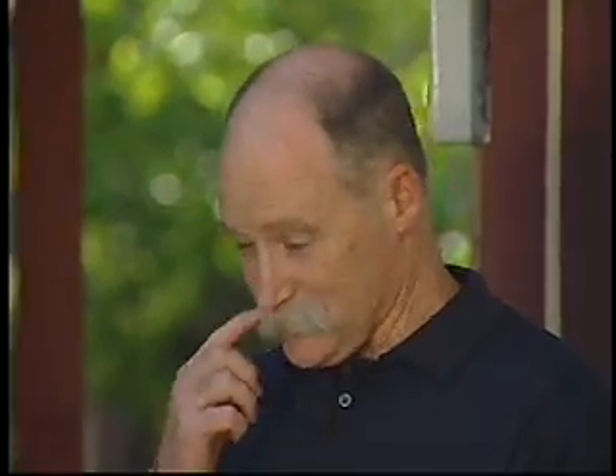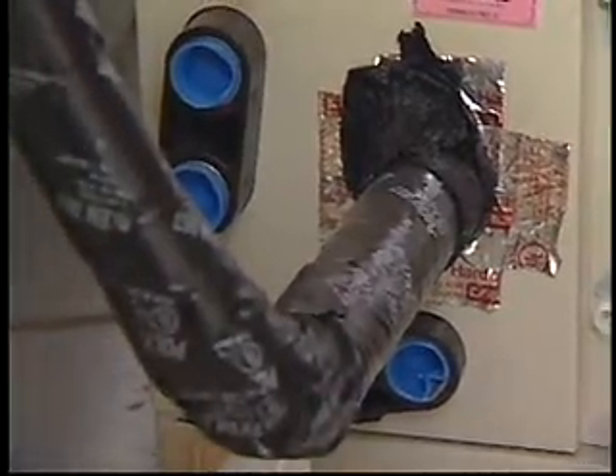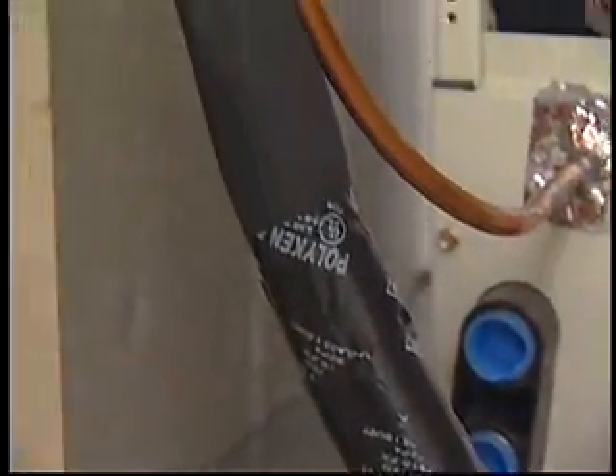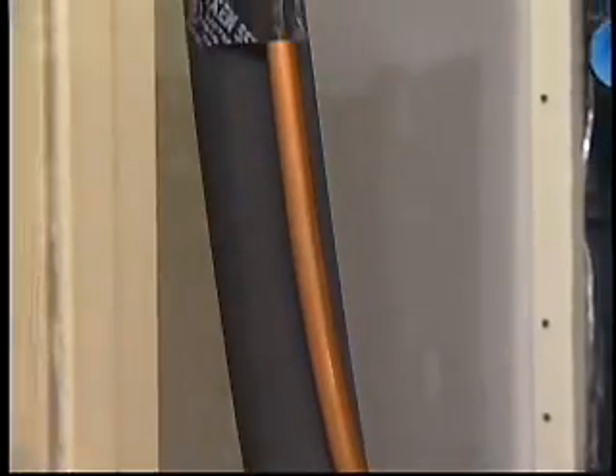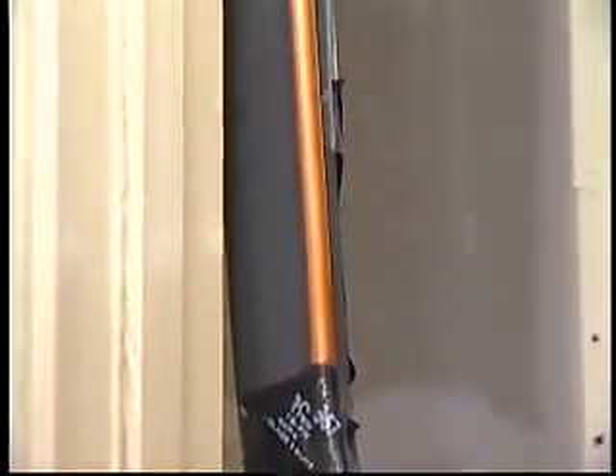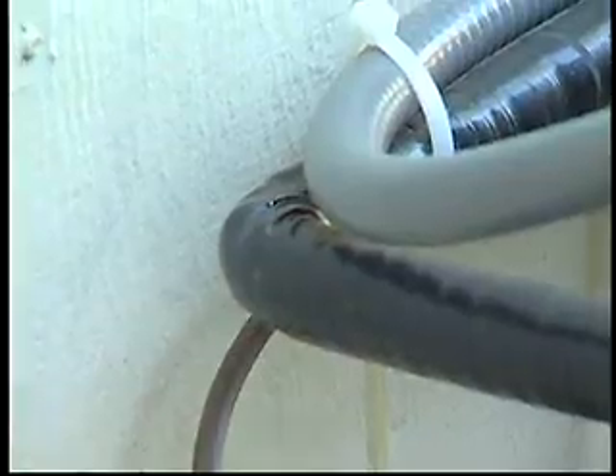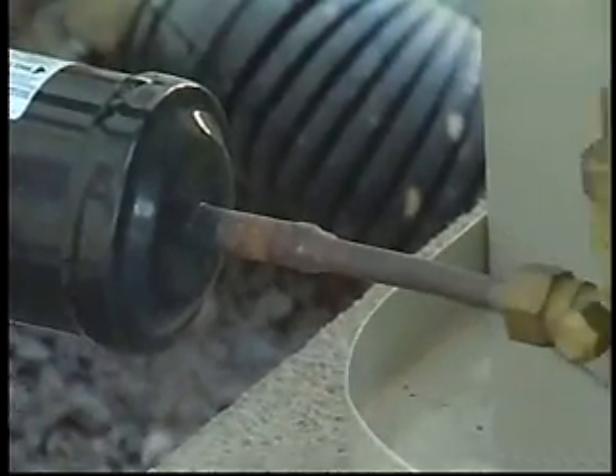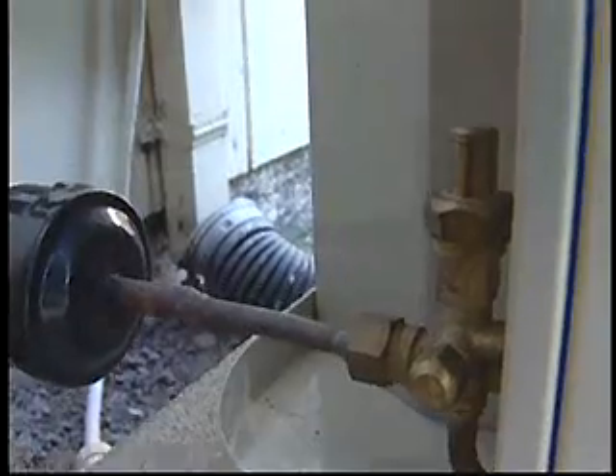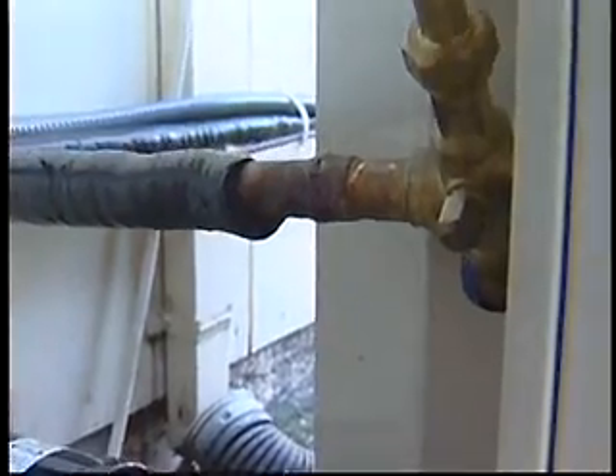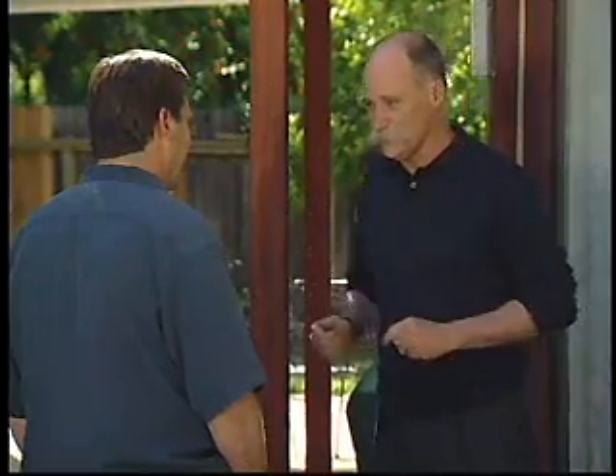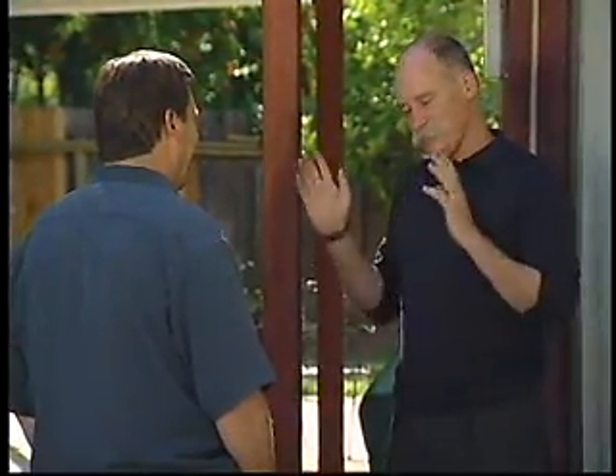What about the size of the line set itself? Sometimes it seems like they run some awful long line sets. Yes, as the line set gets longer, you have to change the diameter of the line set. And again, that's something that all the manufacturers specify, but is most often ignored. In fact, one of the things that you often find is that coming out of the back of the unit, they'll actually use a smaller line set than was even designed for in the first place. And I've actually seen people just take clamps and clamp down, squeeze down the unit, not even put a fitting in there, and then braze it over that leak. So it's pretty amazing what you see.